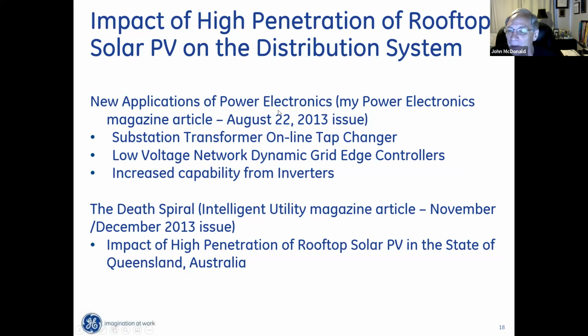The reason I wrote it in Power Electronics Magazine was that I said there are new applications of power electronics. One would be a substation transformer online tap changer, power electronic based, not mechanical anymore. Second is low voltage network dynamic grid edge controllers — we're further distributing the intelligence, putting low voltage power electronic based grid edge controllers on the edge of the grid, and smart inverters.